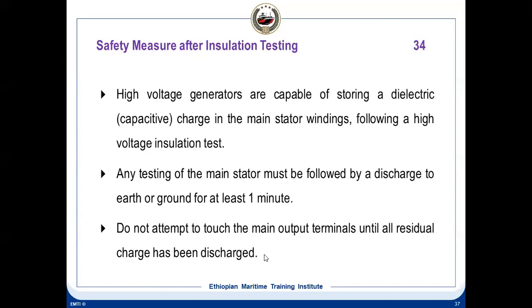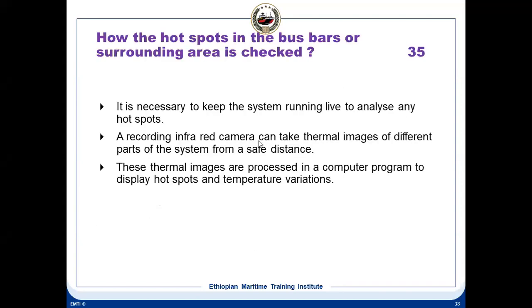So you have to be very careful when you work with high voltage, especially with a Megger. When you use a 5000 volt Megger, you should be very, very careful. Otherwise, it can lead to very dangerous situations, can be a shock or hazard. Okay, these are the safety measures after insulation testing.